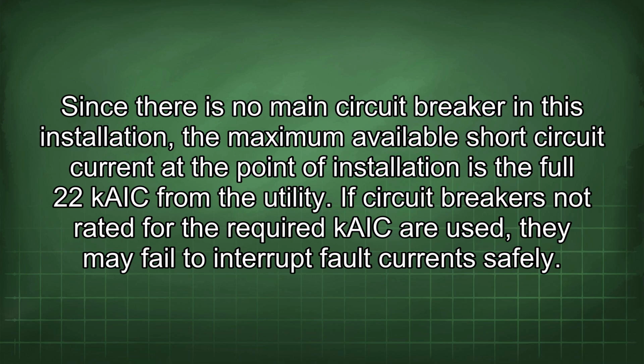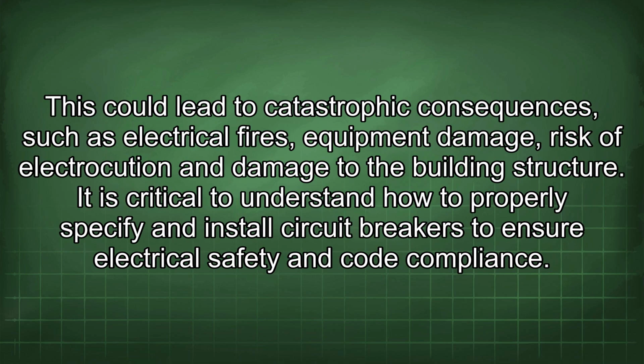If circuit breakers not rated for the required kAIC are used, they may fail to interrupt fault currents safely. This could lead to catastrophic consequences, such as electrical fires, equipment damage, risk of electrocution and damage to the building structure. It is critical to understand how to properly specify and install circuit breakers to ensure electrical safety and code compliance.